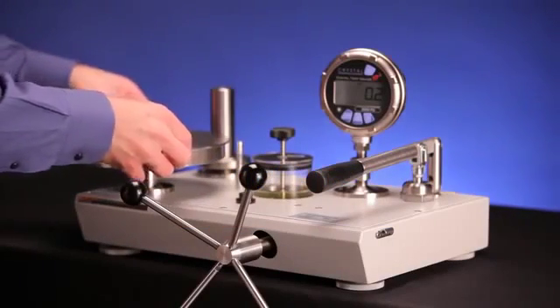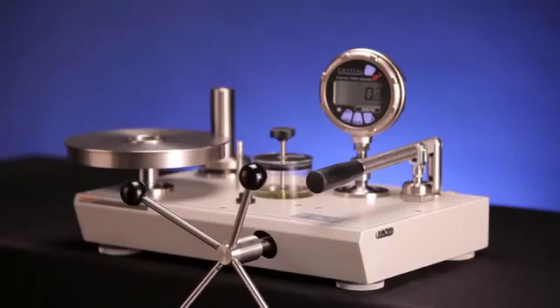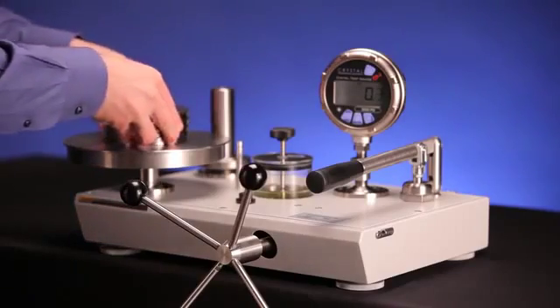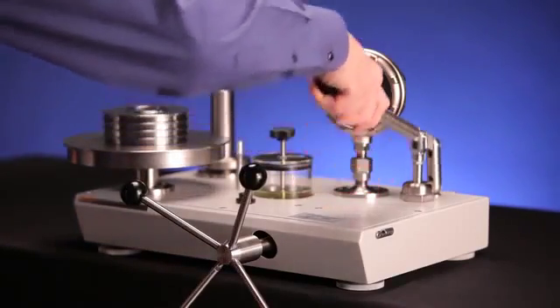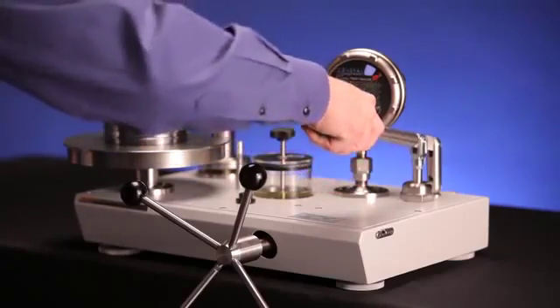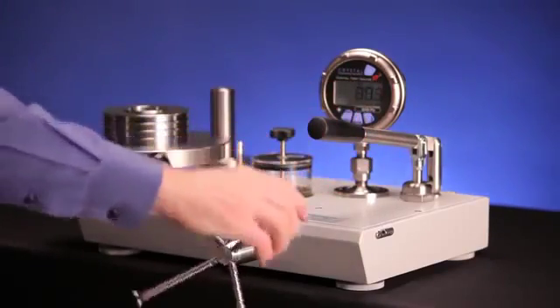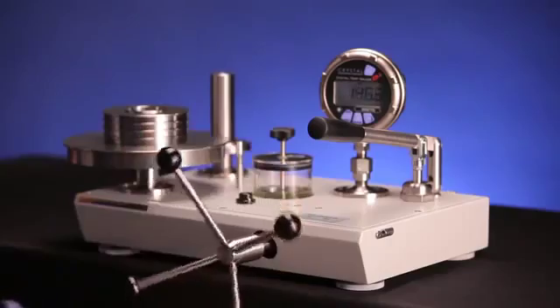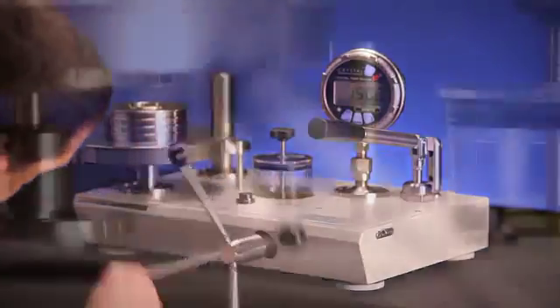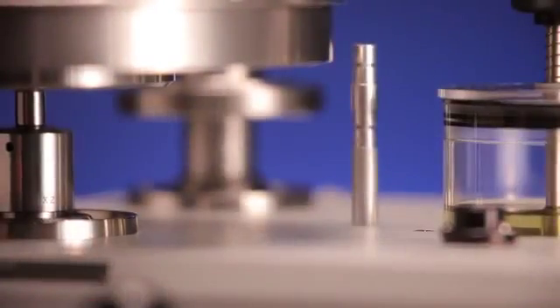To generate pressure, place the appropriate weights on the required piston. Initial pressures can be generated using the priming pump. Then turn the variable volume until the piston is floating at mid-float, as seen using the float height indicator post.